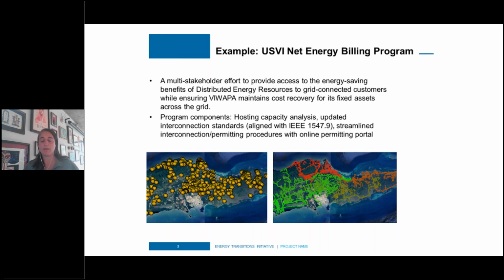feeders. And the image from the bottom right corner is just an illustrative picture of the hosting capacity results. So green feeders obviously have a fair amount of capacity left, and the feeders that are red are nearing their limit. The picture on the bottom left shows where there is distributed solar already installed on customers, either houses or businesses, and these are both the island of St. Croix. So the hosting capacity analysis is allowing the utility to much more easily assess interconnection applications when they come in.